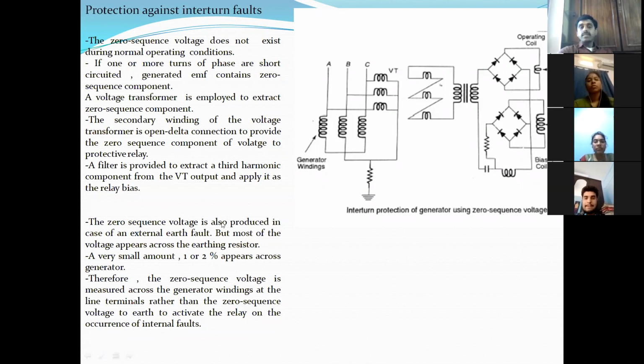Zero sequence voltage is also produced in the case of an external earth fault. Sometimes zero sequence voltage appears not only for the turn to turn fault, but also when there is an external earth fault. Then the relay should not operate. Then what is the condition? Most of the zero sequence voltage will appear across the earthing resistor. Only a very small amount will appear across the winding, that is 1 to 2% of the winding across the generator. That's why for an external earth fault, this relay will not operate.